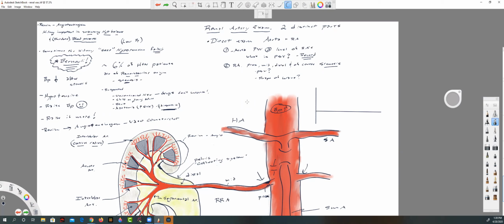Having said that, very difficult because you're probably using a curved transducer, which does not steer. A curved transducer, it's very difficult to get a Doppler angle much less than 60. In fact, it's sometimes just getting to that point is tough. So 60 degrees or better, all the way from the aorta and all the way through the renal arteries.